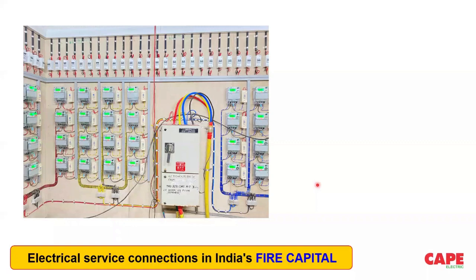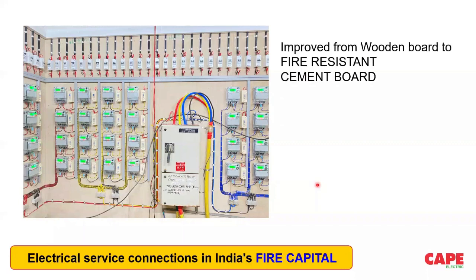So now I show you a small example. Rather than talking about a big safety scenario, we should always start, or my way is to start, from some small things. I'm just showing you the meter board from Bombay, which is used in most of the apartments. There is a meter room, and all the meters and the protective devices are mounted on the wall. The first point to note is that earlier it was a wooden board which was catching fire quite often, but nowadays the wooden board is stopped and fire-resistant cement boards are used. Anyway, congratulations, it's a good thing because the chance of fire on the wood is avoided, but still a lot of existing buildings have wooden boards.